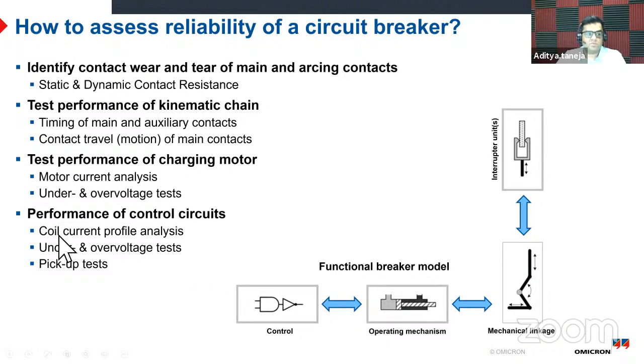And the most important one is the trip coil and close coil, which takes the command from the relay and propagates it to the operating mechanism to operate the breaker. So that needs to be analyzed more in detail. And there are multiple tests which are there.